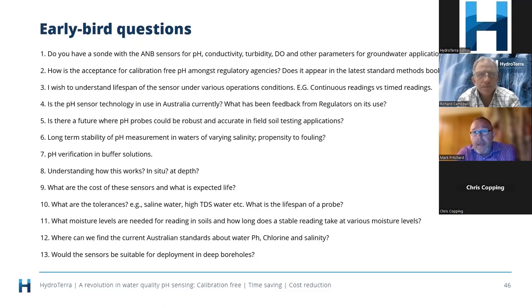Just to recap, a continuous reading for us today is every 23 seconds, that's our reading interval. If you're reading it every 23 seconds, you need to refresh the transducer every 5 days, and then replace the transducer every 100 days. But if you take that out to readings every 15 minutes, you need to refresh the sensor every 52 days, and replace it over 1,000 days, so you're getting close to 3 years. That's just a replacement of the transducer, the sensor itself is still operational, and the transducers are very low cost to replace in comparable applications.